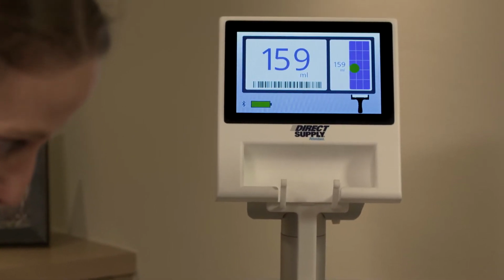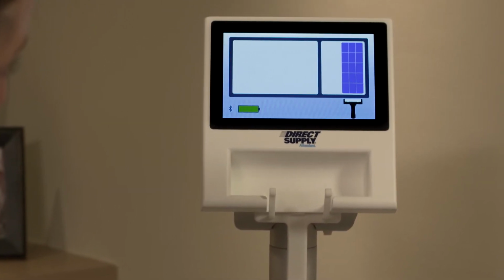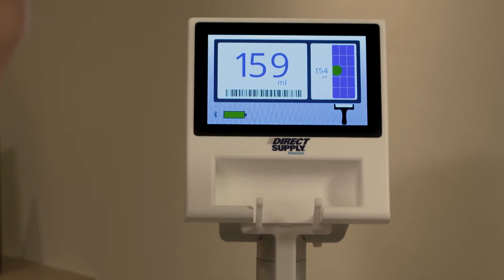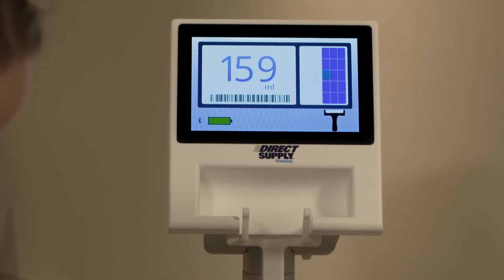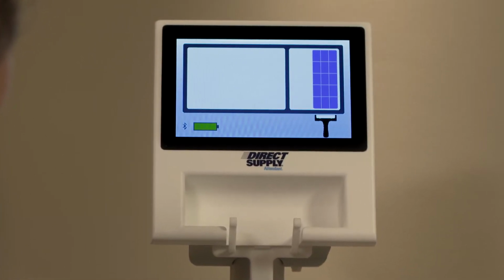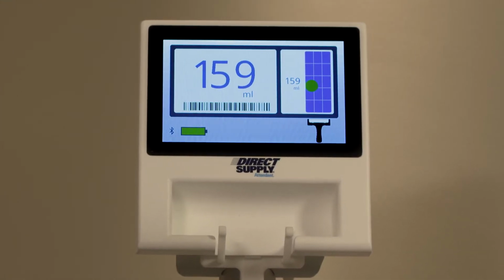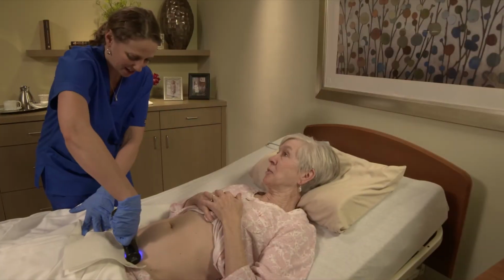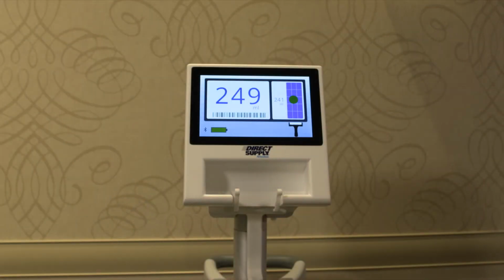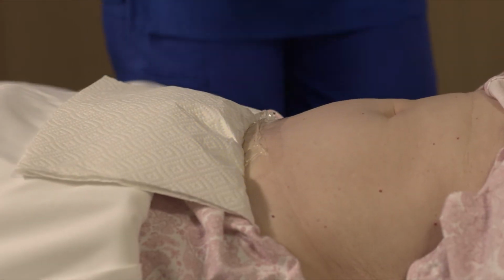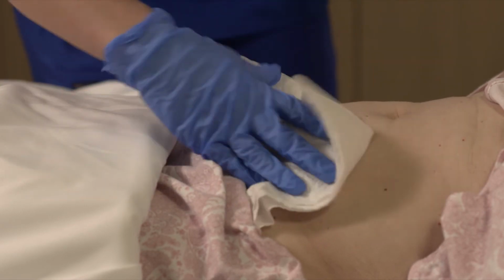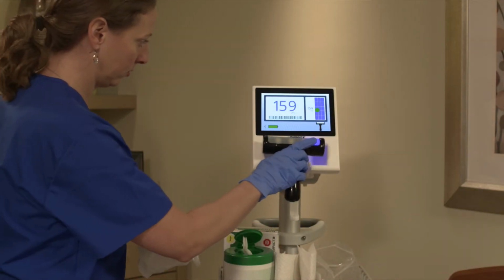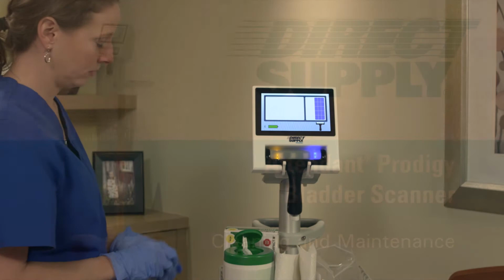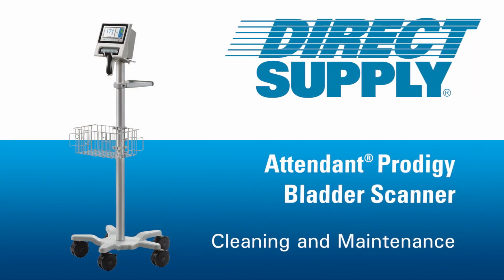If more than one measurement is taken, the largest volume measured during the session is displayed on the left side of the screen. The current reading in the session is displayed on the right side of the screen, alongside the bladder projection. The console and probe can wirelessly communicate up to 30 feet from each other. To close out the session, remove the scanner probe from the resident, clean and return it to the console. For cleaning instructions, see the cleaning and maintenance video.